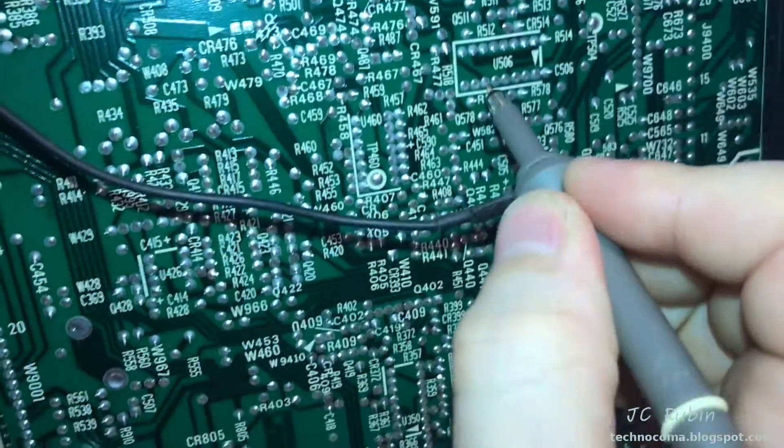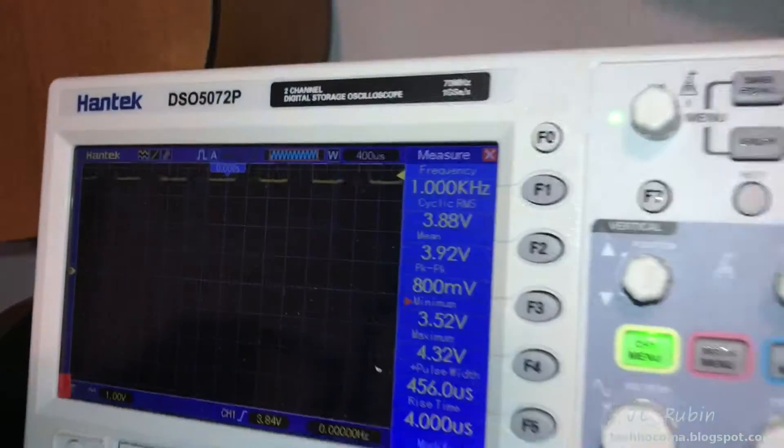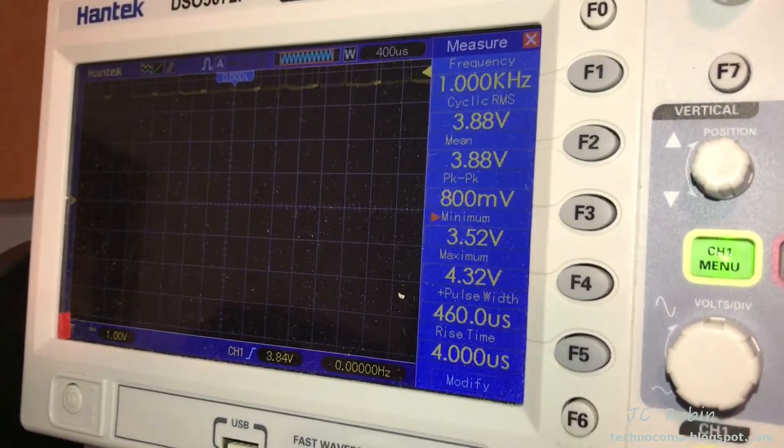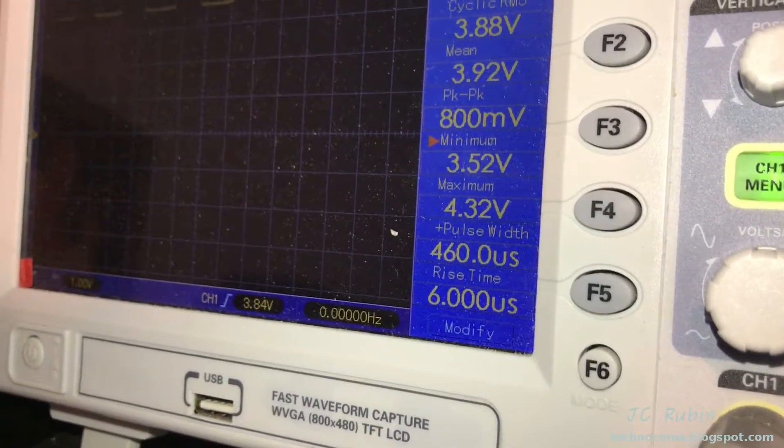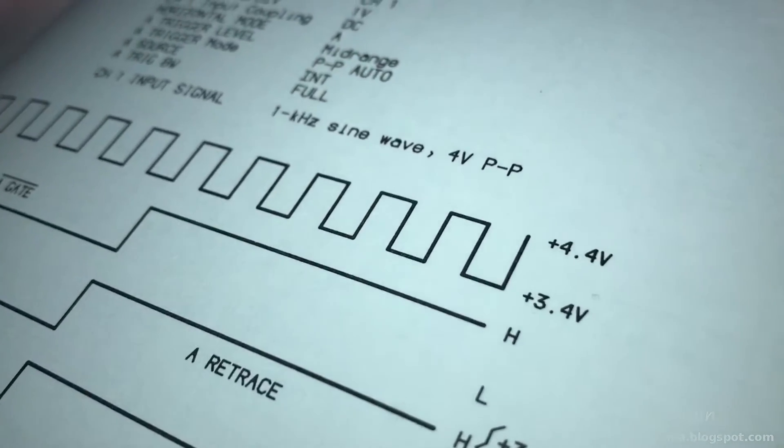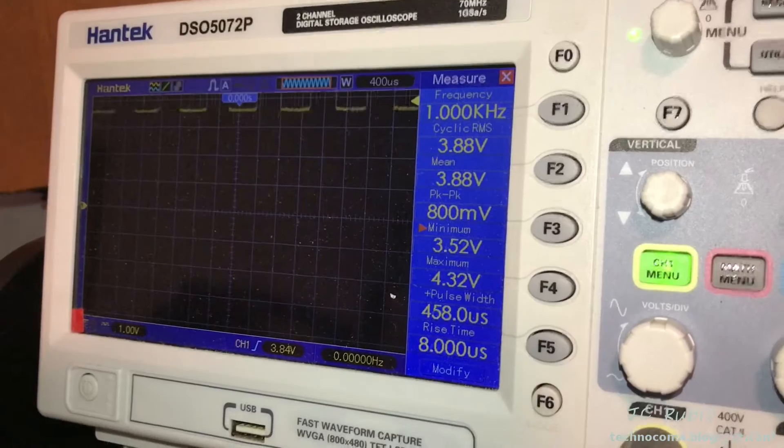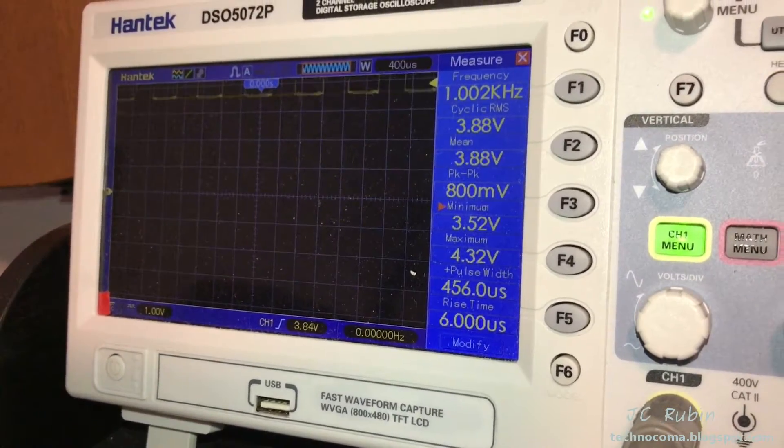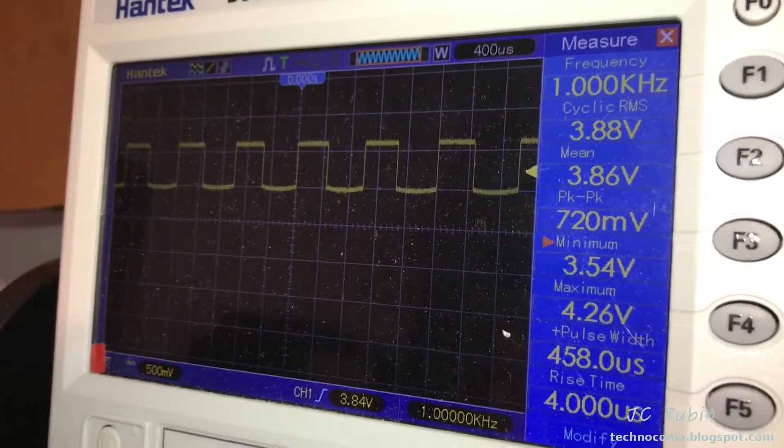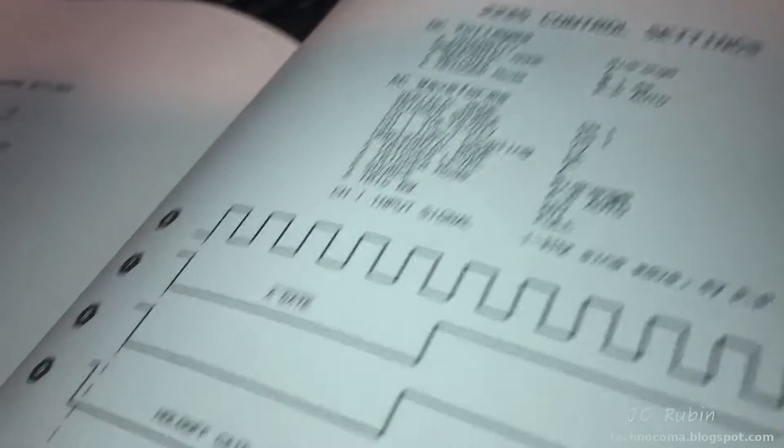I'm going to move on to number one, which is test point six. It sits on U506. While you can't see it on my oscilloscope because it sits a bit high on the screen, you can see the measurement there shows 3.52 to 4.32 volts, and we could see 3.4 to 4.4. It's a nice square wave. I brought it down just so you can have a better look at it. I'm going to say that test point six looks good.